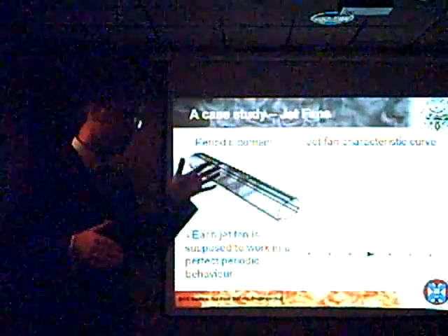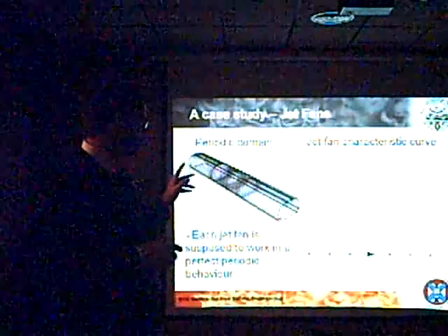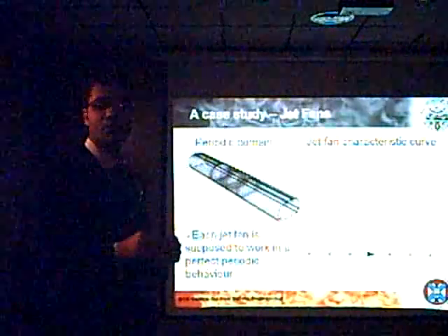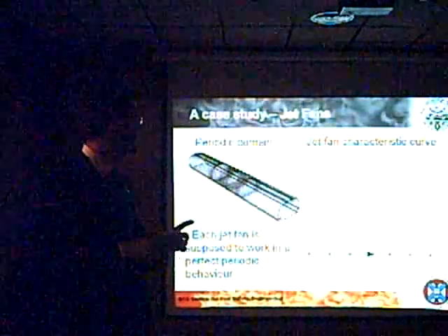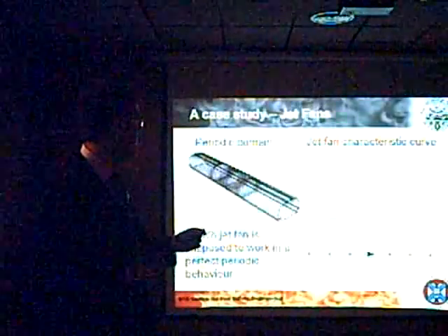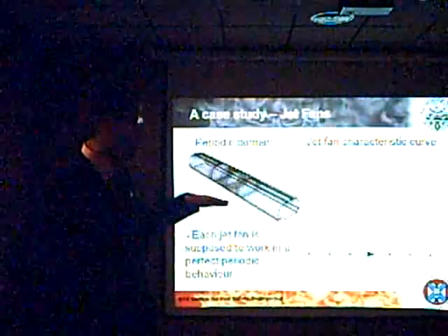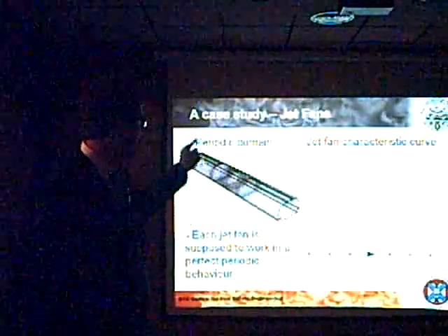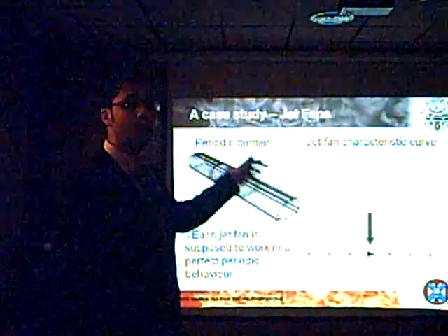In this case, it was 50 meters long, with a periodic boundary condition between the beginning and the end of our region. Once we built our model, we did many simulations and reconstructed the final results in terms of bulk flow quantities. In this case, we had pressure rise and average velocity through the domain. And we got a curve like this one. So in my network model, anytime I have a fan, I know that the behavior of this fan has to be like that one.